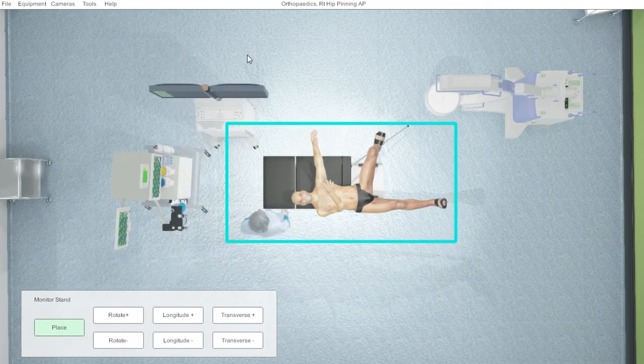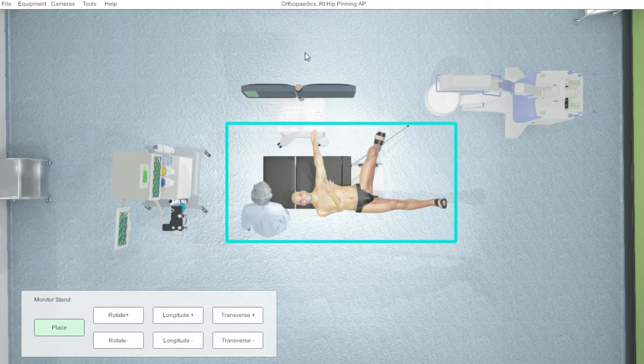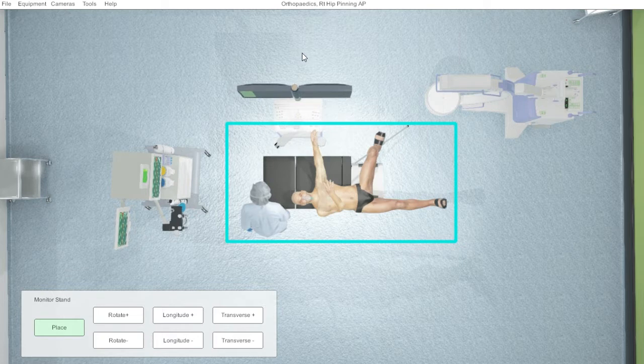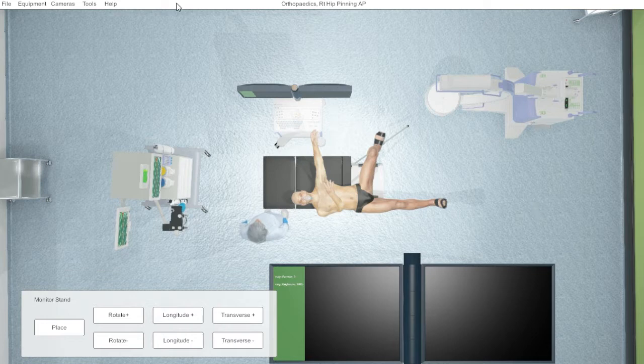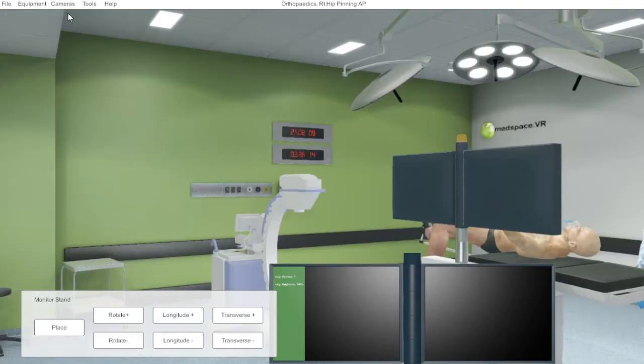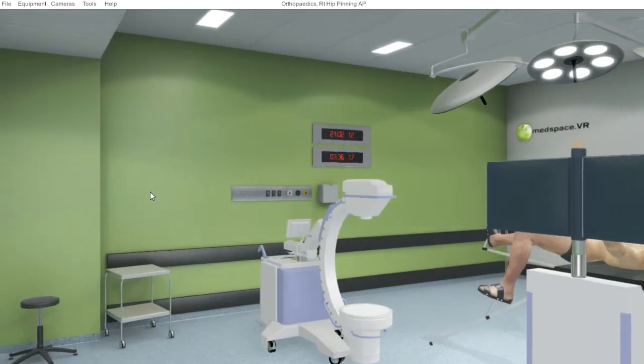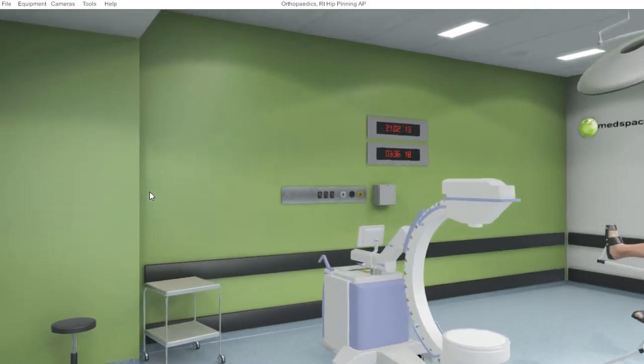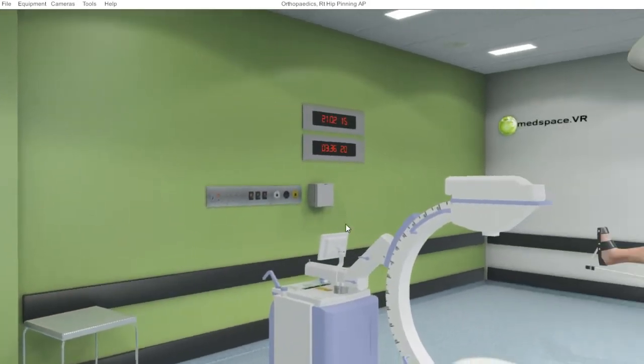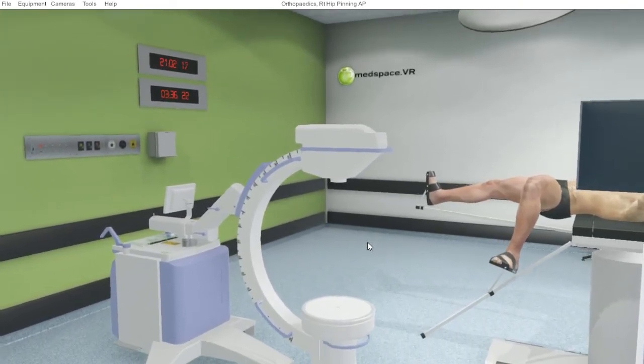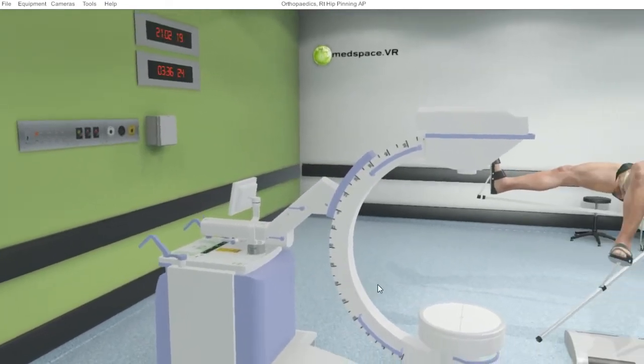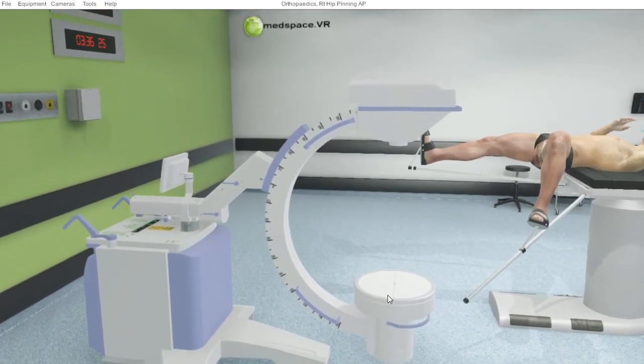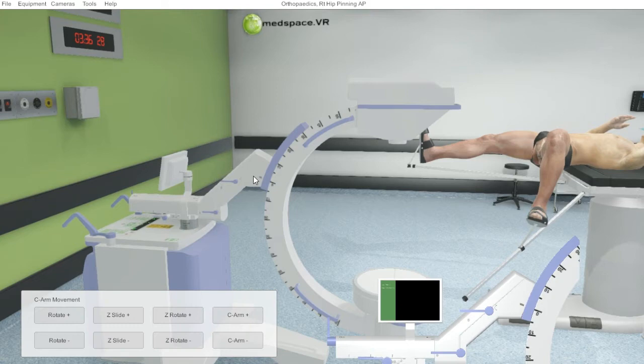Monitors can be placed in the same way as the base of the C-arm and then you can move back to the radiographer view in order to manipulate the C-arm. As with surgical procedures, the radiographer needs to think ahead and position the C-arm appropriately with either the tube or the detector at the top. This clearly needs to be done outside the sterile field and before the surgeon is ready for you to image.